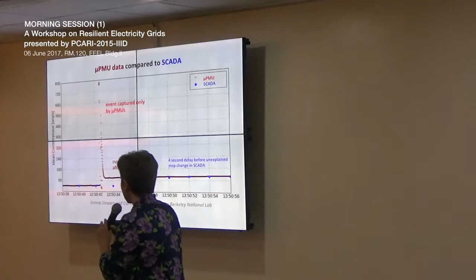Oscillations were really the prime motivation for PMUs in the transmission system, because when you think about what's going to cause really wide area outages, it is going to be wide area power oscillations and generators tripping offline, cascading failures because you exceeded some relay setting. And so this is just an illustration that we can measure those kinds of oscillations. This is one utility that I won't name, but they asked us to install micro-PMUs at their very large generator that was having some issues, and we helped them diagnose their issues.